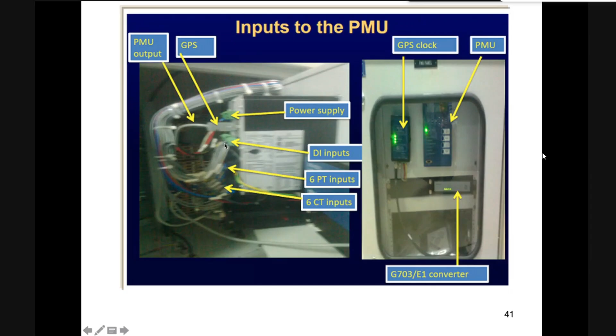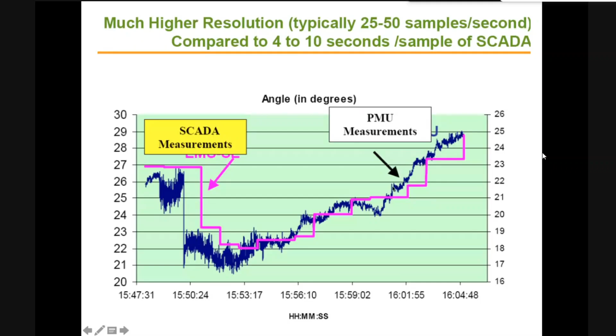This is a comparison between SCADA measurement and PMU measurement. The sampling rate is typically 25 to 50 samples per second for PMU, but only one sample every 4 to 10 seconds for SCADA. During that gap, the system doesn't know what has happened - any element may have failed, or a ground fault may have occurred, but it won't be reflected in SCADA measurement. All this data will be captured if PMU is implemented.